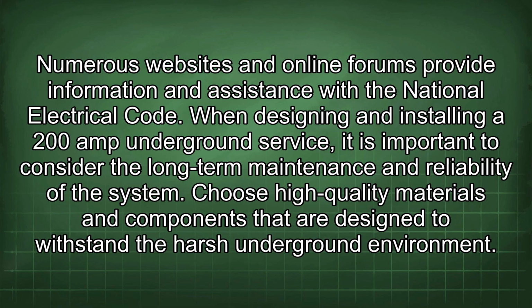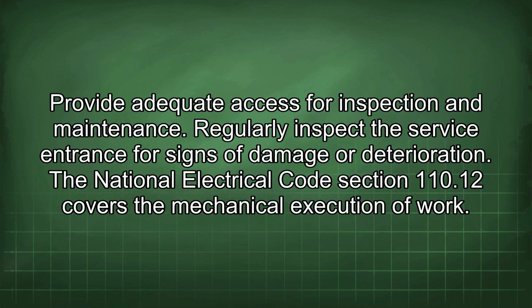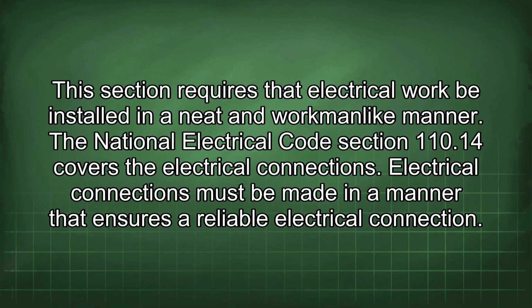When designing and installing a 200 amp underground service, it is important to consider the long-term maintenance and reliability of the system. Choose high-quality materials and components that are designed to withstand the harsh underground environment. Provide adequate access for inspection and maintenance. Regularly inspect the service entrance for signs of damage or deterioration. The National Electrical Code Section 110.12 covers the mechanical execution of work. This section requires that electrical work be installed in a neat and workmanlike manner.